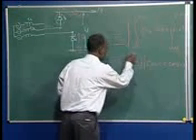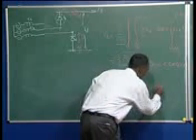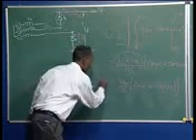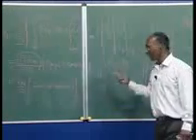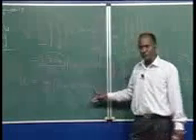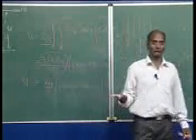Now you can find this component was our VDO. So I can write here VDO by 2 times cos alpha plus cos alpha plus u. This is the DC output average voltage across this link in case of mode 1, that is, when valve 1, valve 2 and valve 3 are conducting simultaneously. Now if we put u equal to 0, we get the same expression. When u is 0, the 2 cancels, and Vd is nothing but Vdo cos alpha, which we derived for the ideal case when only 2 valves were conducting.